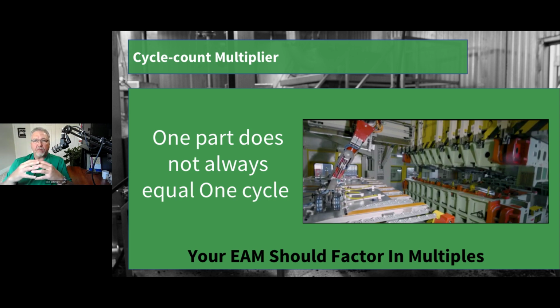What our software has allowed us to do is to have what we call a cycle count multiplier. So in the software, you can actually factor in this cycle count multiplier. Hey, it takes 3 cycles of this machine to build 1 piece of product. So we want to factor that in by 3. So every time the thing cycles, it counts it correctly inside of the system. And then we can set our PMs to that. And that also does that on the opposite.